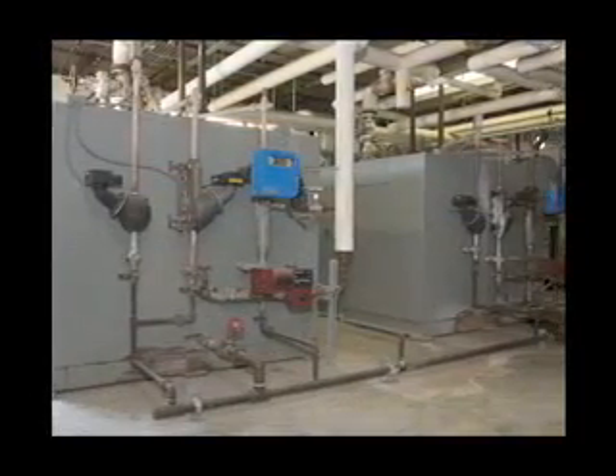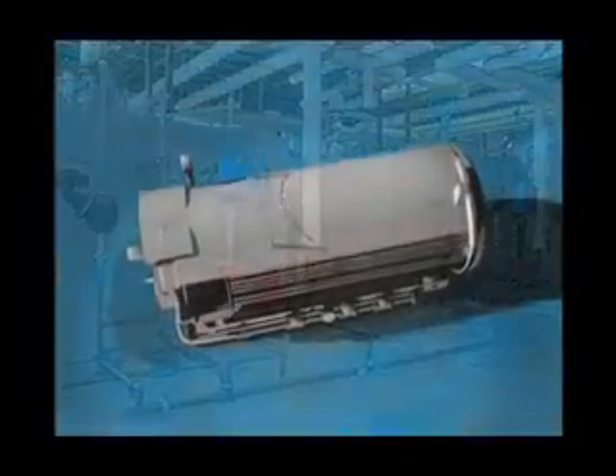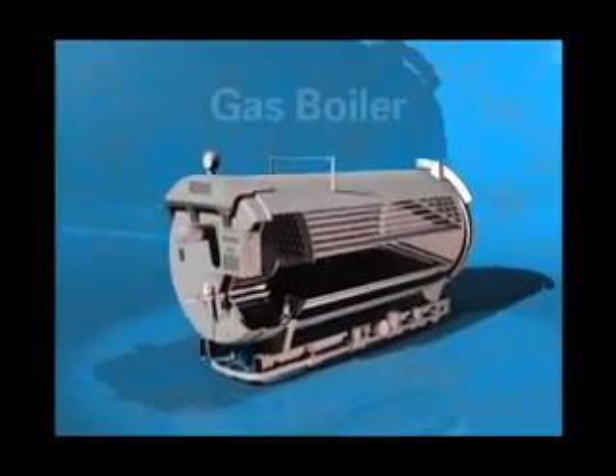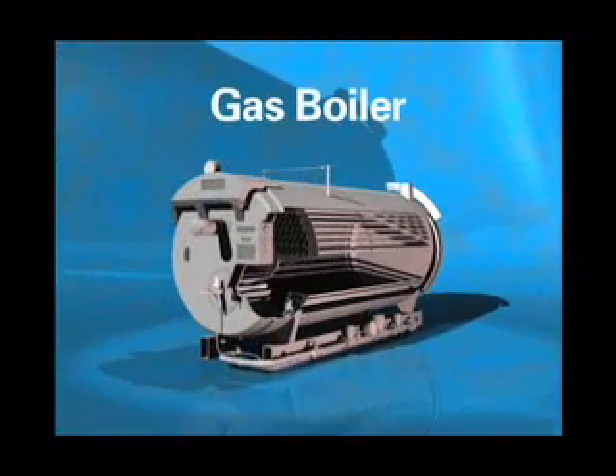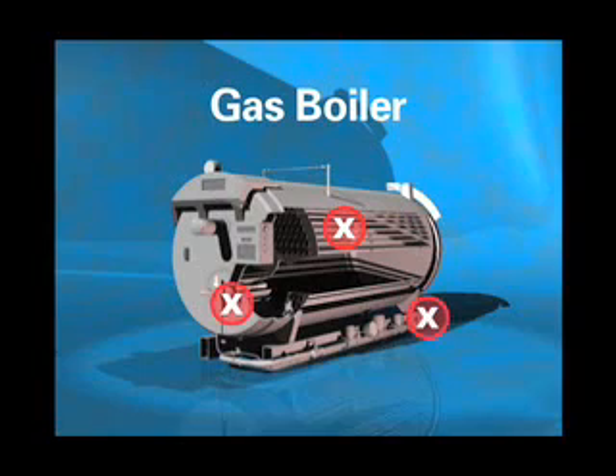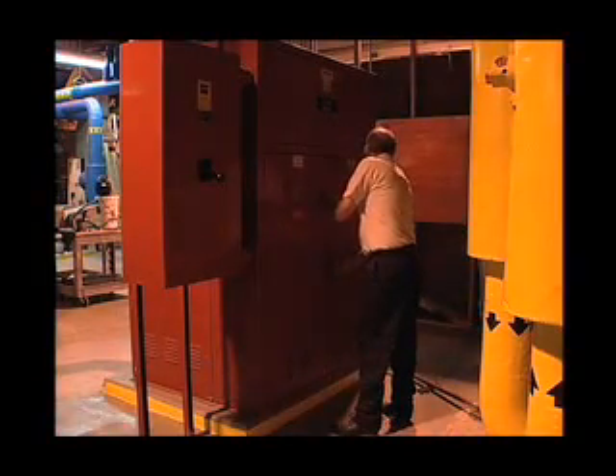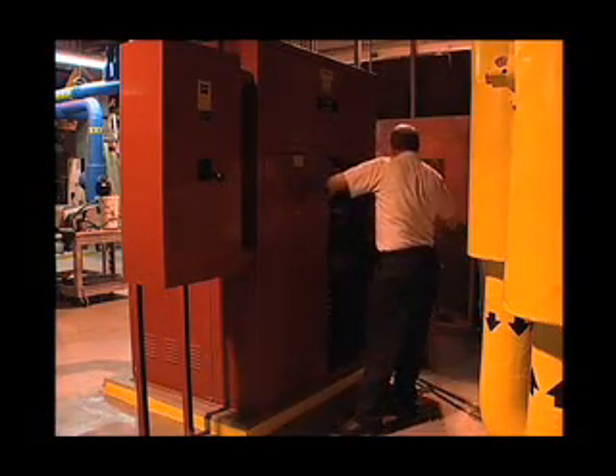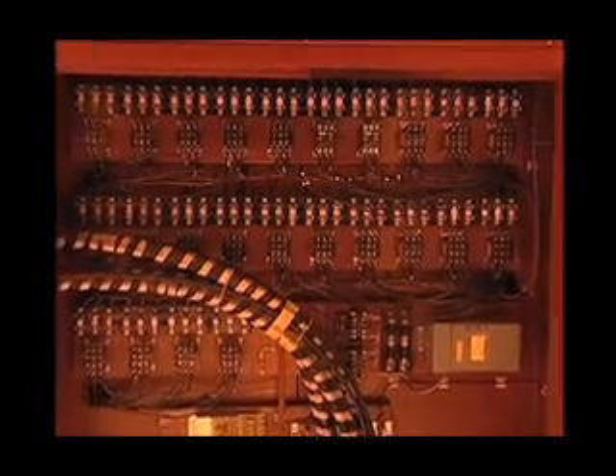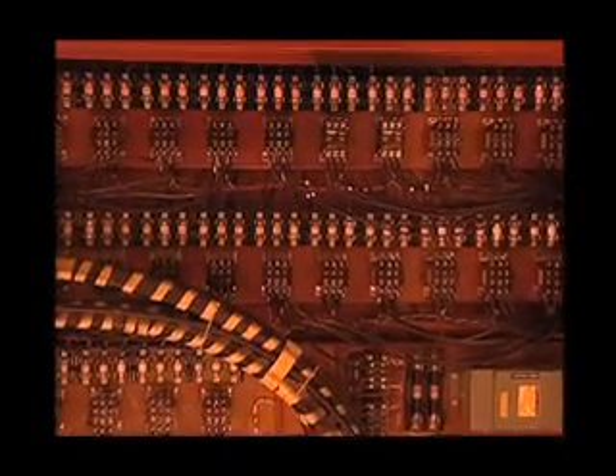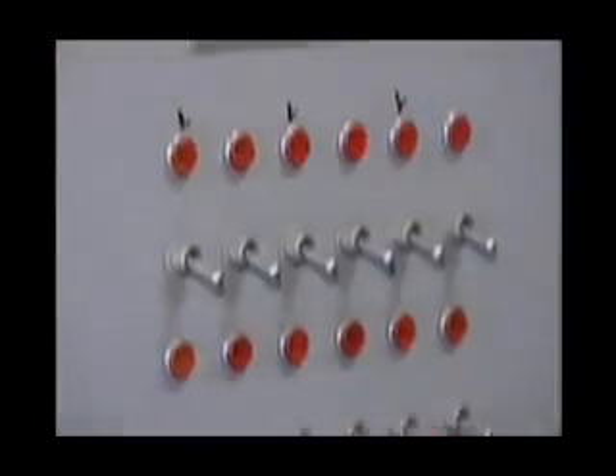I've got a boiler. Why do I need two? For reliability, so you'll always have hot water or steam when you need it. Electric boilers don't need a lot of maintenance. No corroded tubes to clean or replace, no burners to adjust, no leaks to plug, and no fan or mechanical controls to break down. Electric heating elements are simple to replace, either individually or in bundles. And the controls are solid-state electronics, not clunky mechanical cams or linkages.